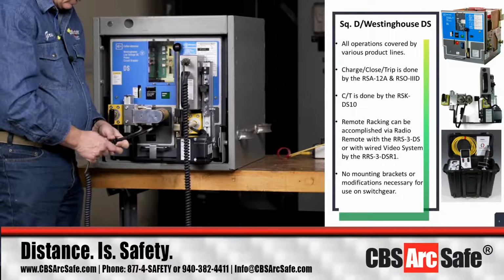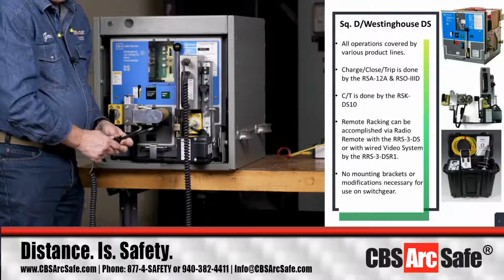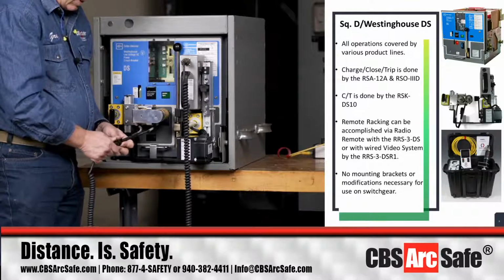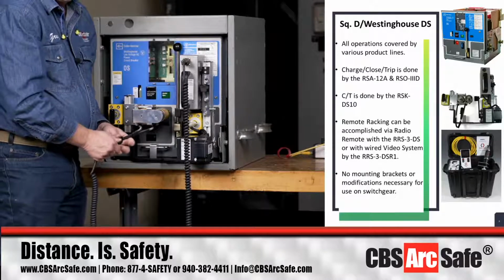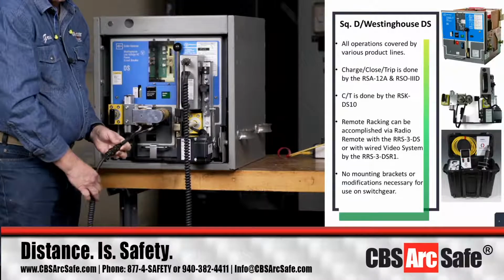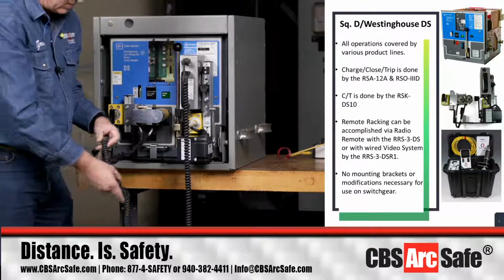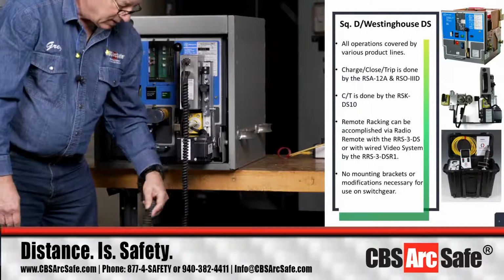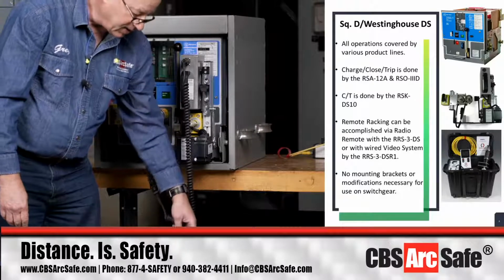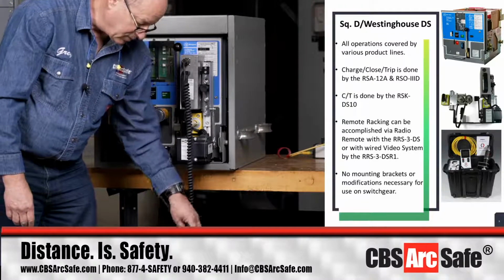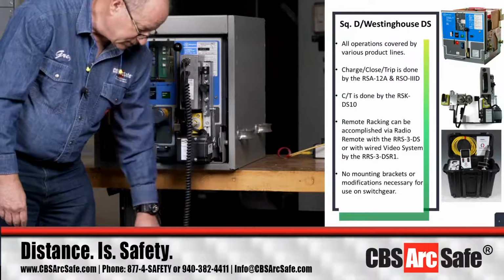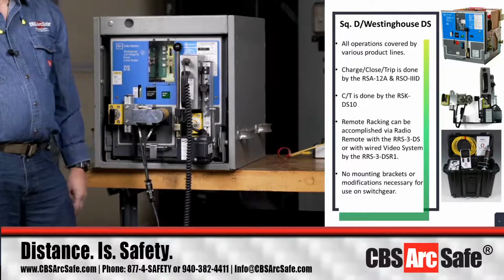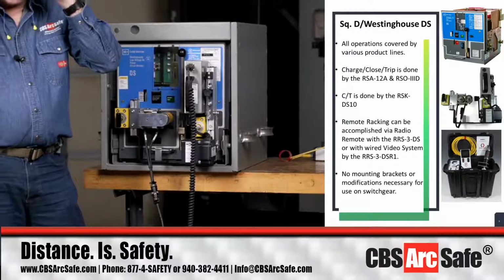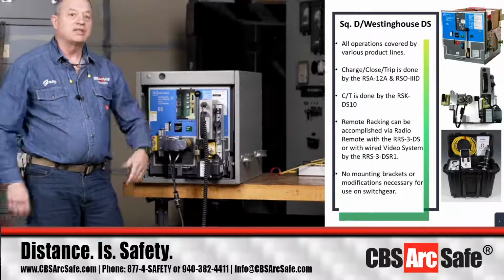We were like, oh. So if you've got a motor with worn pawls that's not properly charging your breaker, and it won't charge, and you're having to manually crank it, and you don't have time to take that circuit breaker out of service, this is something you may want to consider as an addition to your lineup. We'd still recommend you contact one of our sister companies within circuit breaker sales to get the circuit breaker serviced.